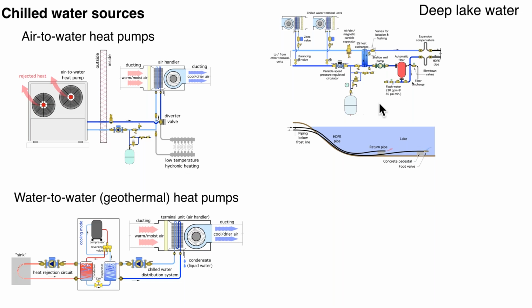And the system up here is basically using some type of an intake that's supported up from the base of this lake. We don't want to be sucking in silt and dirt from the bottom of the lake. And we've got some kind of a pump that's pumping that in. This shows an automatic filter. These products are out there that can automatically detect when the filter media loads up, and then they can use domestic water pressure to basically flush themselves out. And of course, what we're doing is trying to protect the heat exchanger. We don't want crud in that heat exchanger. And then that water is returned back to the lake.